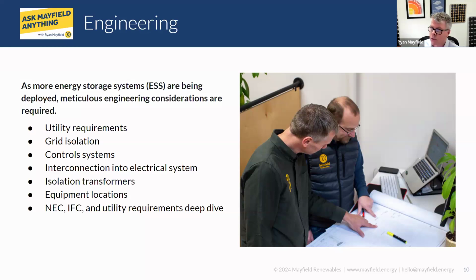Before we move on, there was a question about NEC, and I just can't help myself whenever a code question comes up. Haley did ask about 702.4, 2023 specifically. For those not familiar, 702 is optional standby systems in the National Electrical Code, and Article 702 is going to come into play for our systems. 702.4 talks about the ability for the backup system to power whatever loads we're backing up, and there's a couple different ways - in 2023 there's some language change, and we can do a manual transfer.